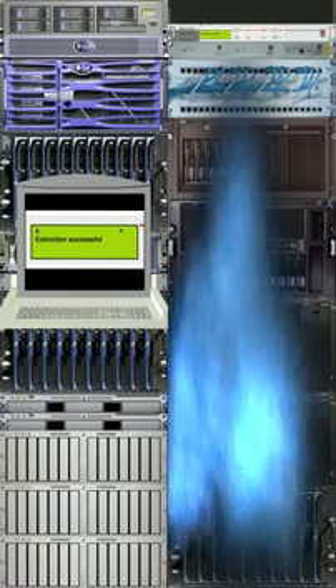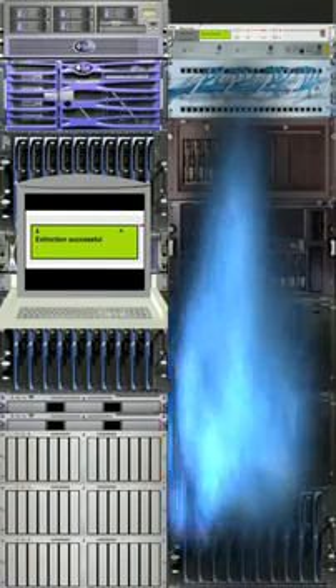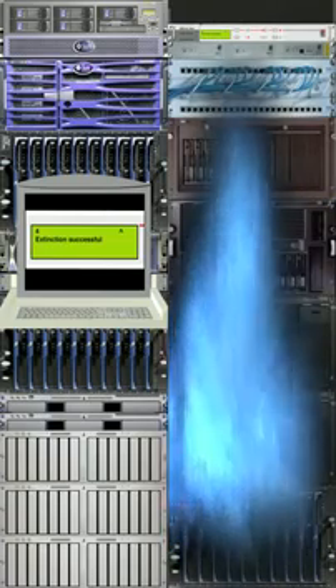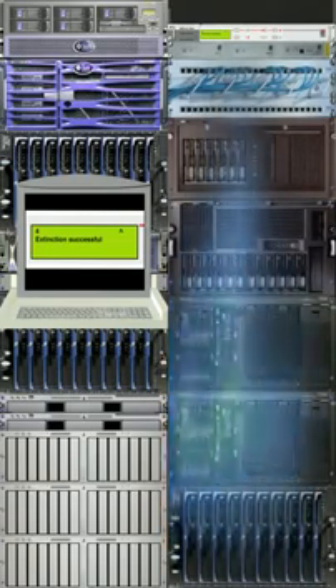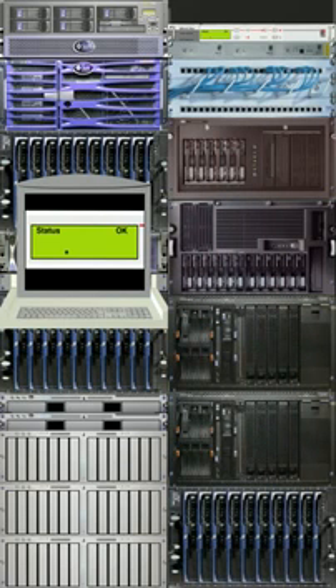Not only does Novec 1230 fluid meet today's regulations, but sensitive hardware such as servers, storage and switches aren't impaired by the extinguisher medium. Due to the rapid detection of smoke, even in racks with a high level of airflow, this ensures that there's plenty of time to forward an alarm message either acoustically, optically via the liquid crystal display, or by connecting the volt-free contacts to the building management system or fire alarm center. In the event of a mains failure, the integral battery backup maintains the fire detection system for 4 hours, ensuring that protection is provided even in the worst of cases.